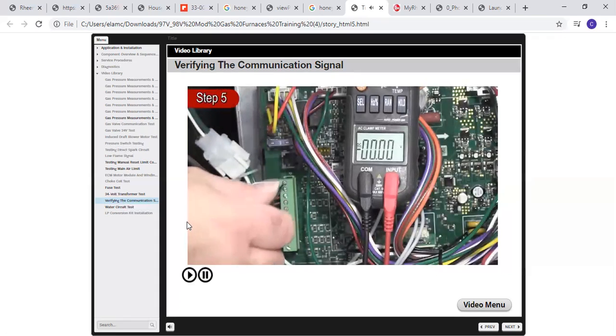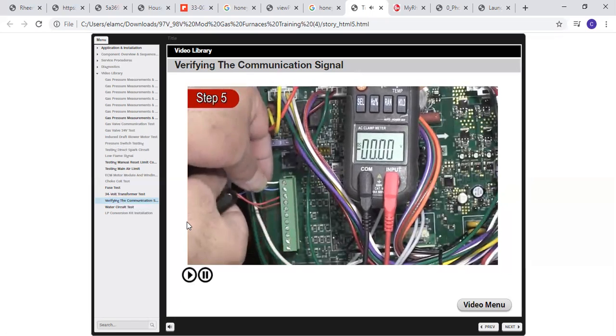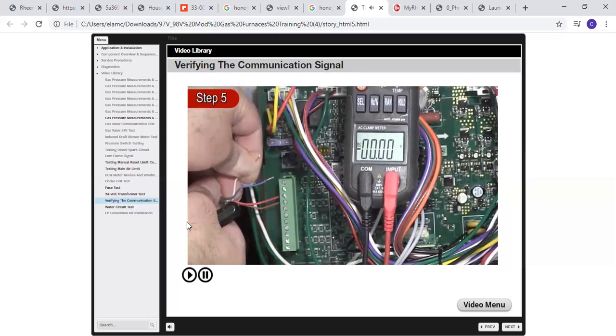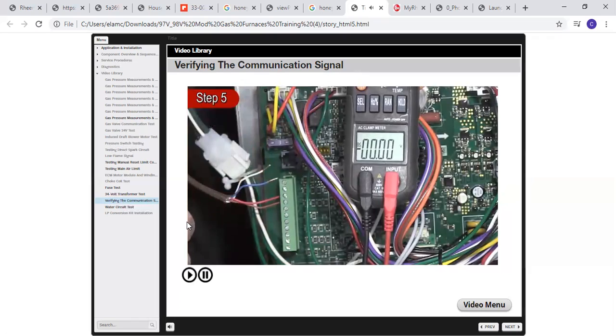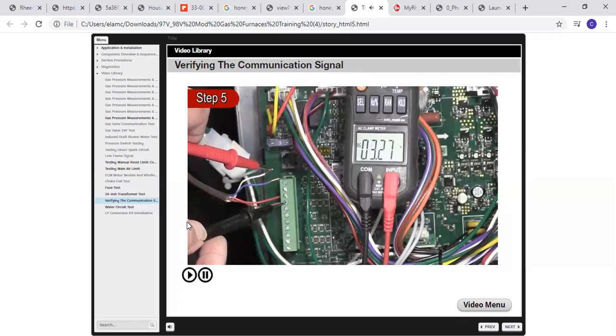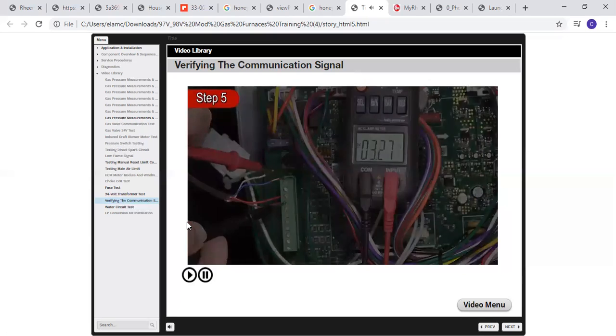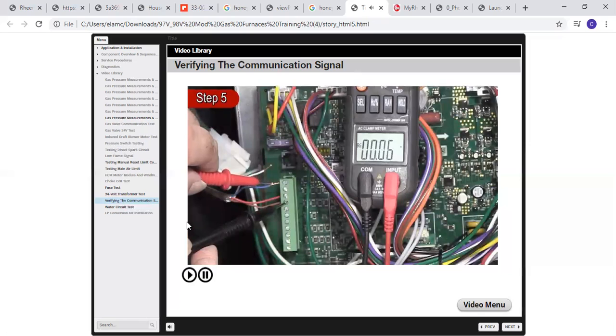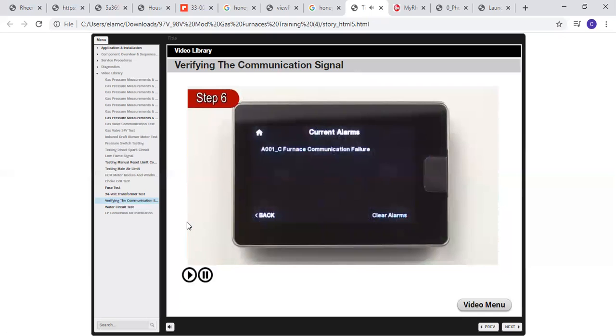Step 5. To confirm that the wired controller is trying to communicate, disconnect wires from terminals 1 and 2 of the furnace terminal block. Leave the 24 volts AC, R and C, connected to the wired controller. Check the wired controller to verify the communication signal is present. Wire 1 to C will have a fluctuating voltage between 2.5 to 3.5 volts DC. Wire 2 to C will have a voltage that will vary between 0.3 to 1.8 volts DC. If the voltage reading is not present, replace the wired controller. Step 6. The wired controller will display a communication error if a loss of communication is sensed.